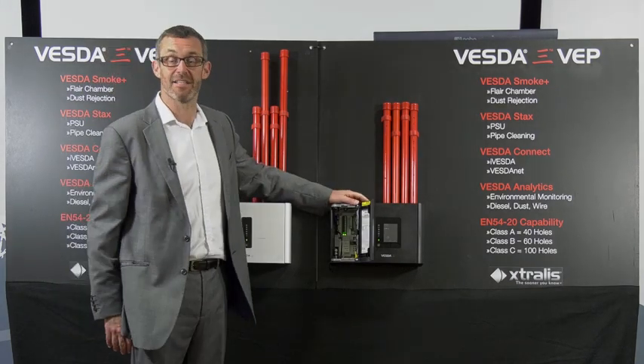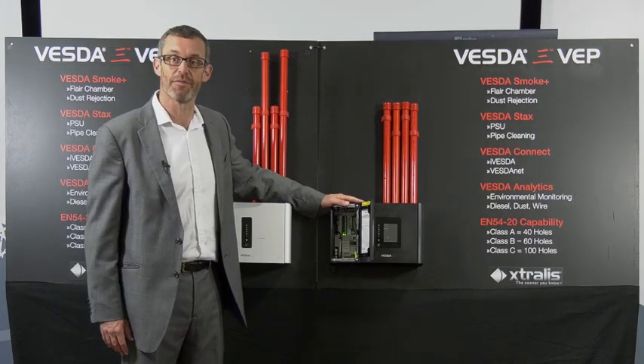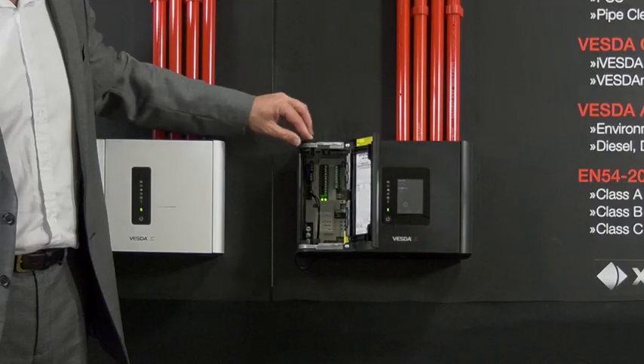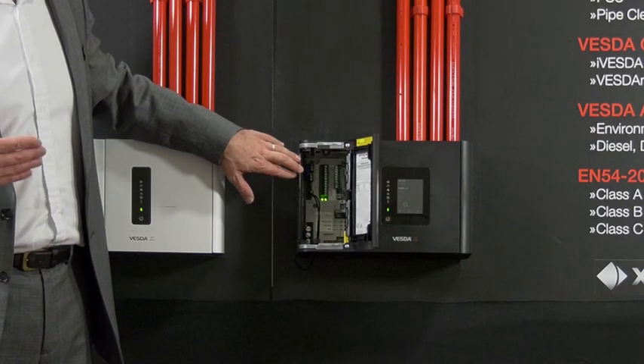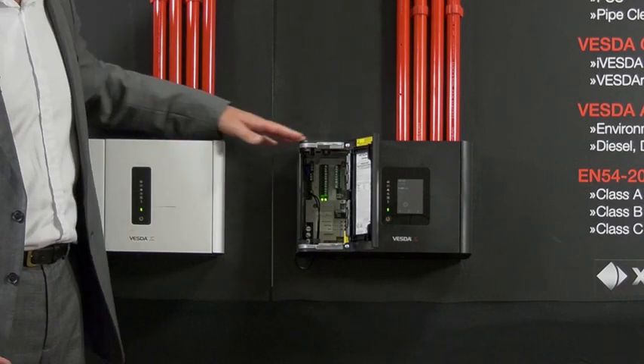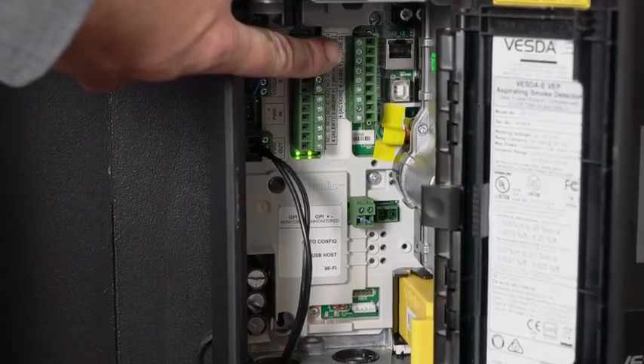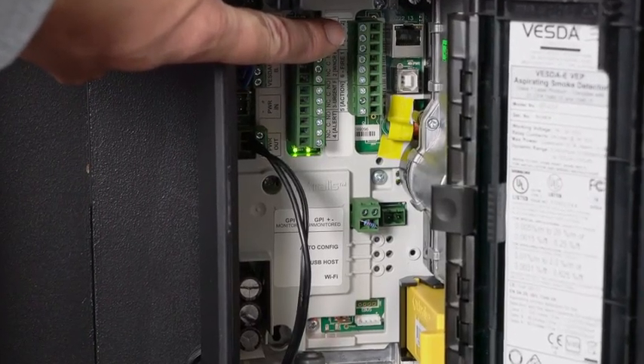The VESDA detector needs to connect to a fire alarm system. Same as the current range of VESDA product, we use volt free contacts inside. From a backwards compatibility point of view, the VEP and the VEU have exactly the same cable connections as the laser plus product, so it's a very easy retrofit.